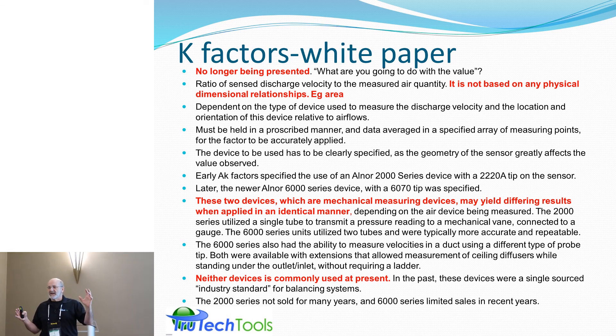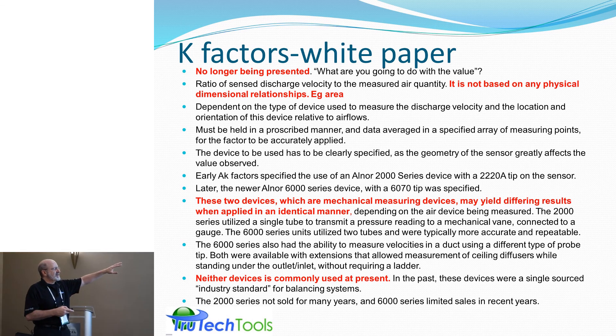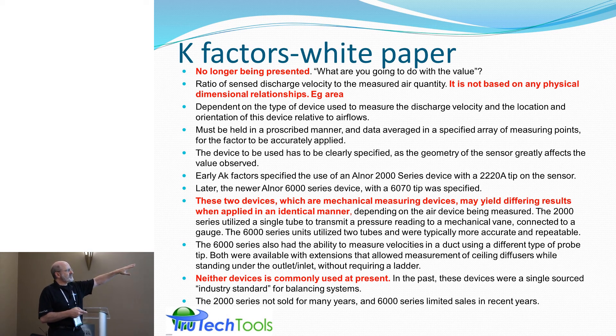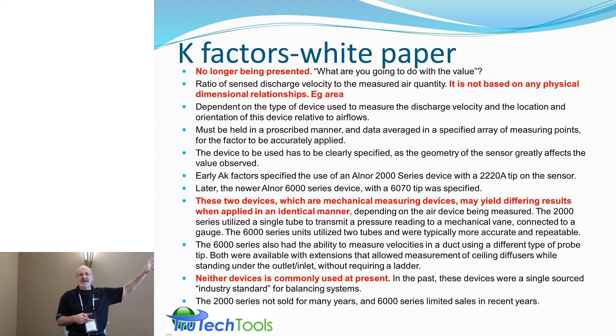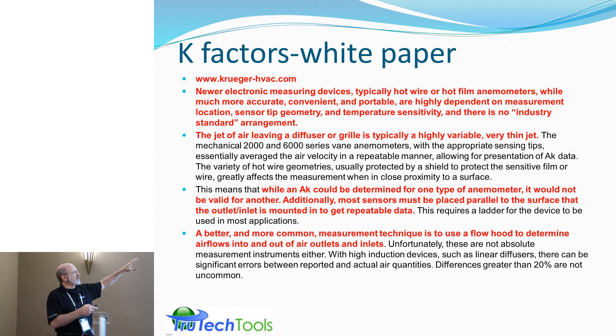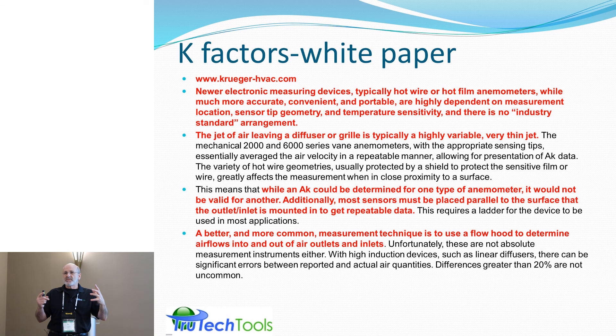If you see a K-factor on a grill, it's probably an older design grill or older curriculum. Be aware you're looking for open area when doing these tests. The two devices that were industry standard at that time yielded different results when applied in the same manner, and neither is presently being used. So be careful when using the standard grill K-factor. Kruger HVAC at krueger-hvac.com wrote this white paper — just Google 'K-factor grill airflow' and it comes right up.